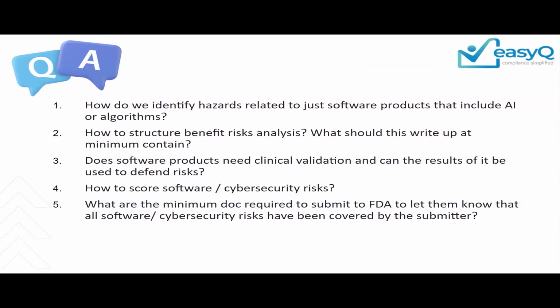Please look into that. It has n number of requirements from a documentation perspective. It starts from maintaining your bill of materials, doing your threat modeling, defining a cybersecurity procedure, and having a cybersecurity maintenance plan. Before that guidance document came into the picture, as a thumb rule and good practice, I used to recommend that when you do your VAPT testing, vulnerability and penetration testing, at least submit reports which are not more than a year old. Now with the mandate of submitting your cybersecurity maintenance plan, which is similar to your software maintenance plan, you will have to define the frequency in which you're going to do all these activities.